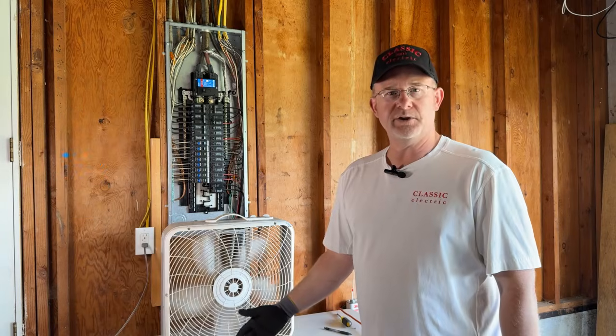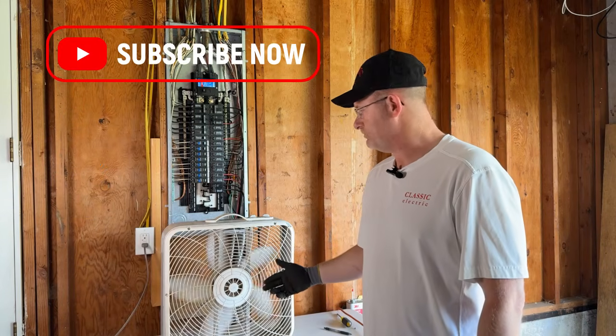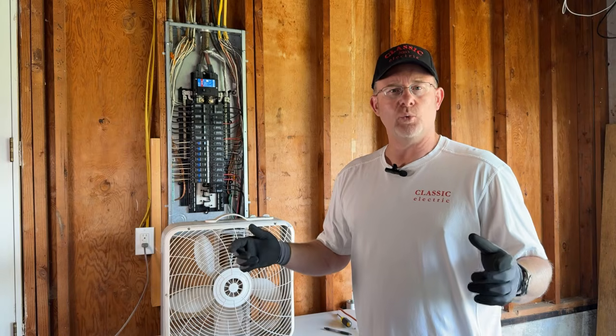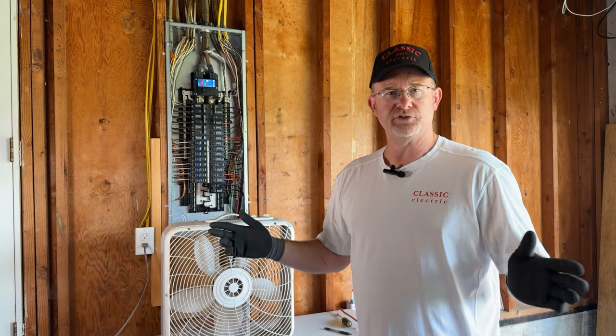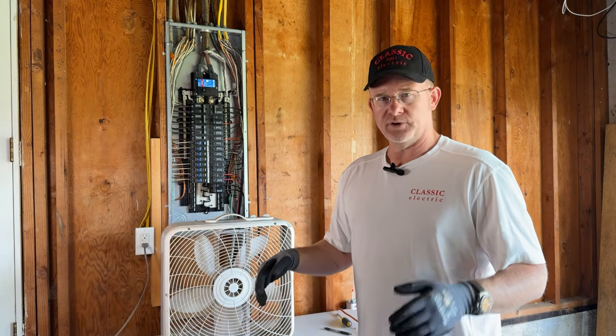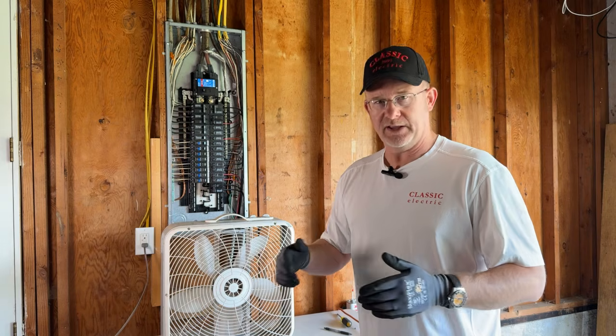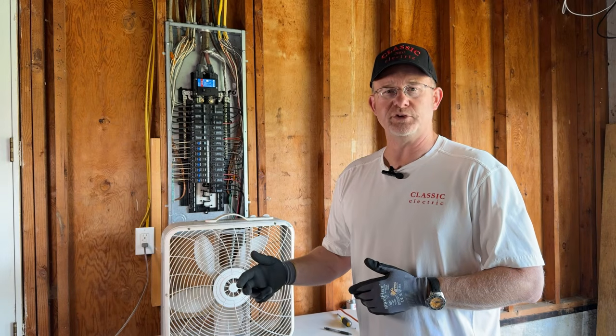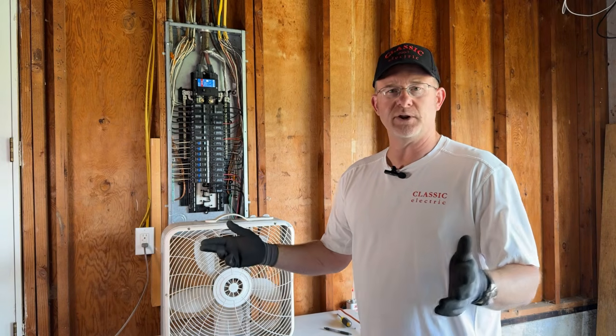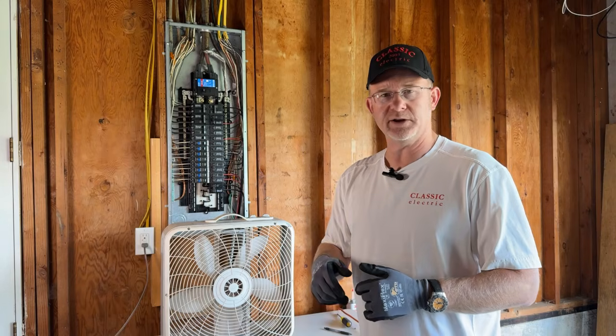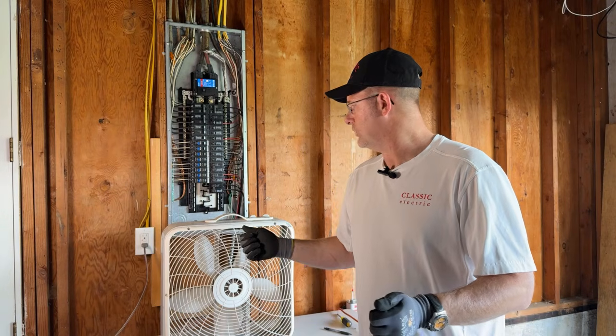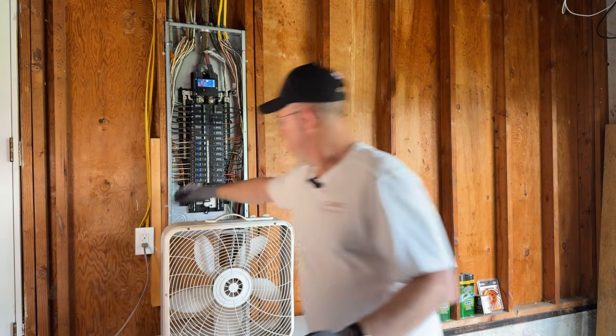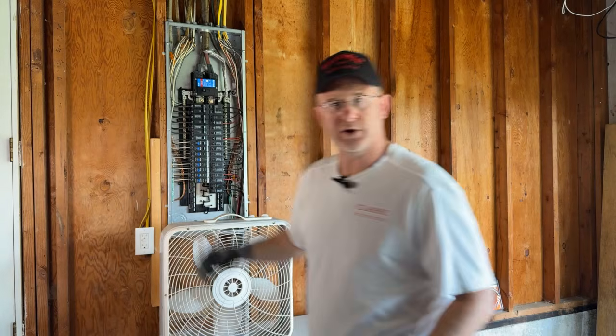which makes for a really nice test when somebody calls me on the phone, for example, and says, and this is very common, I get this a lot, "I have a water feature in my backyard and it's tripping the GFI." Okay, well, if it's tripping the GFI, usually it's because the pond pump is bad. And so I'm on the phone with them and I just say, okay, unplug the cord and do this simple test, which we're going to do right here.